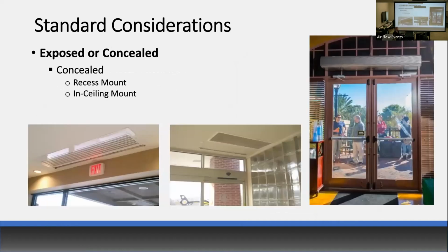Other considerations, aesthetics. Is an exposed unit going to work? If not, if we're dealing with architects, they don't want to see it. Are we going to have to do something in ceiling? Always, it's best if you can have that air curtain discharge nozzle as close to the door header as possible for performance. Sometimes that's not an option. So if we are going above the ceiling, you'll see that nozzle is not directly over the opening.